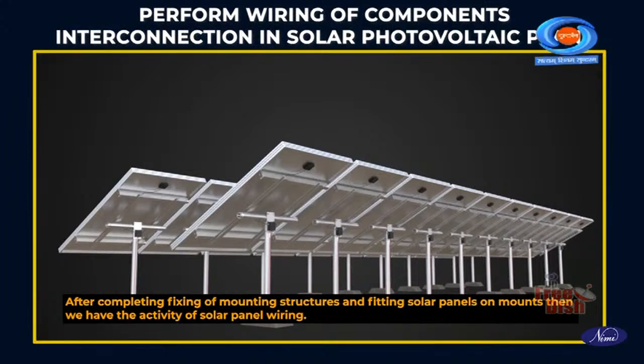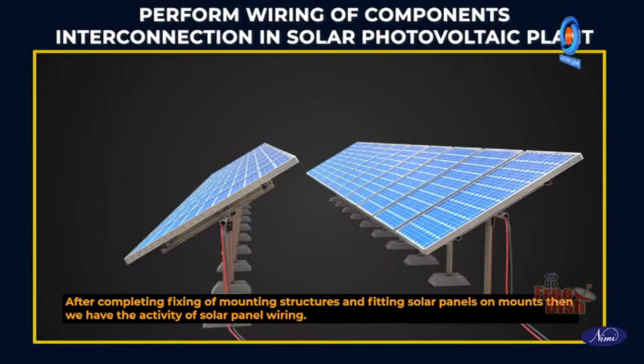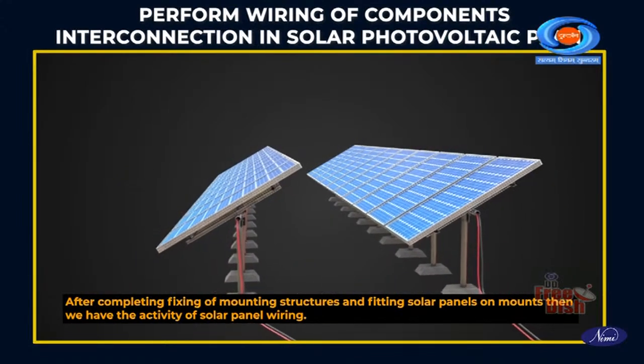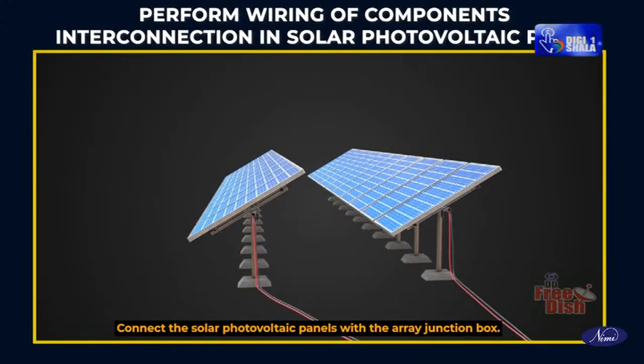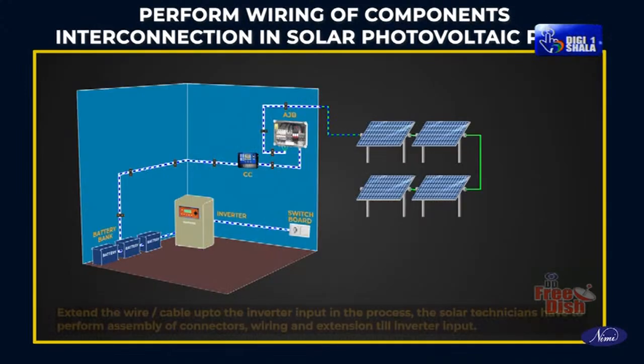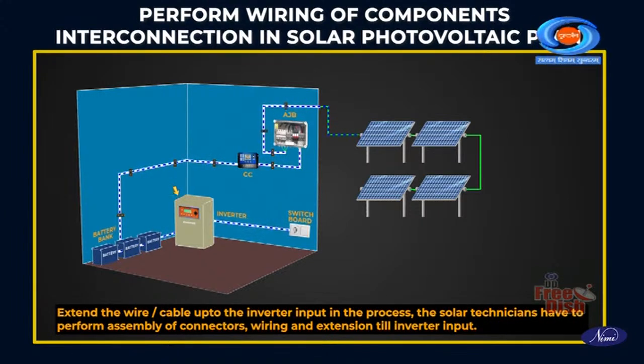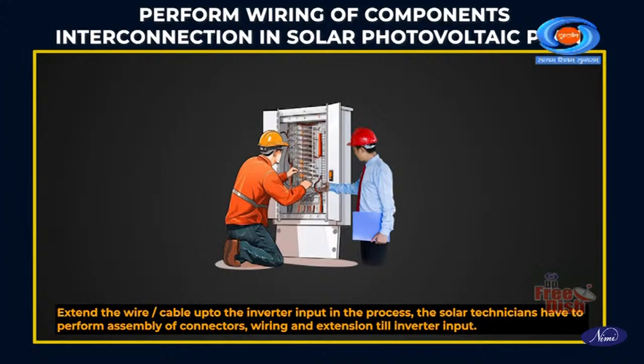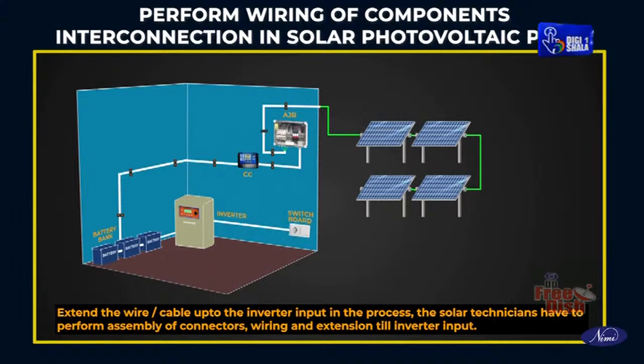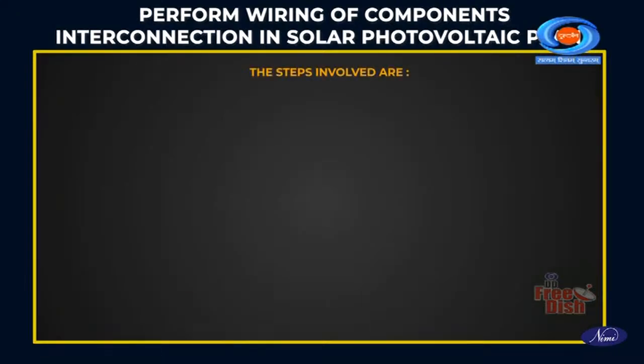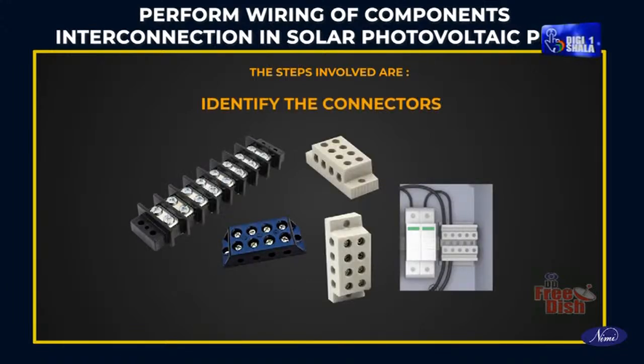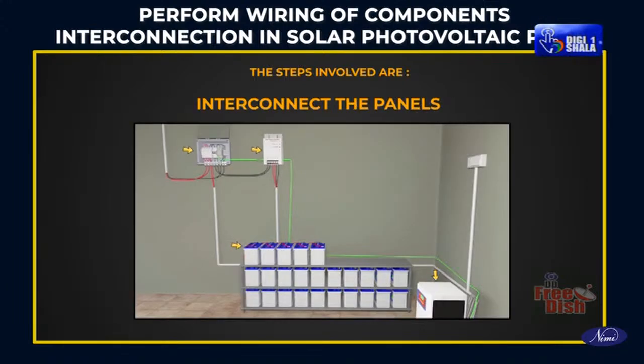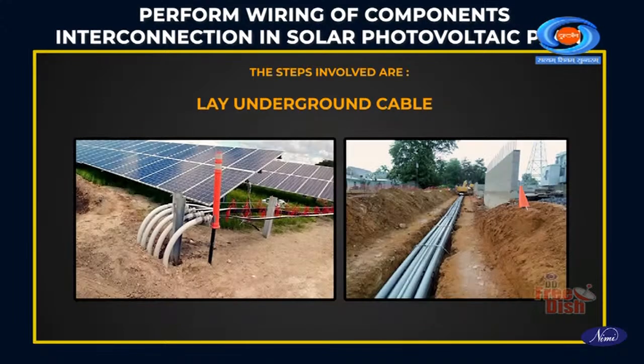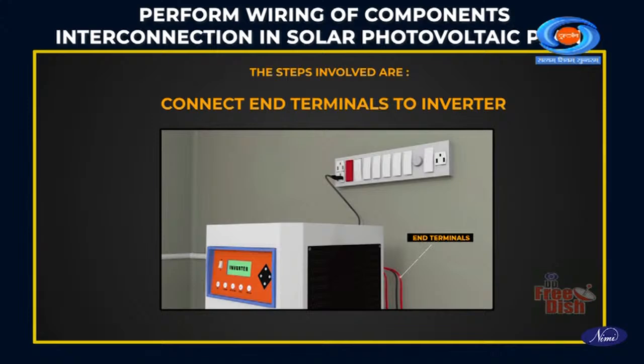After completing fixing of mounting structures and fitting solar panels on mounts, we have the activity of solar panel wiring. This involves connecting the solar photovoltaic panels with the array junction box. Extend the wire or cable up to the inverter input in the process. The solar technicians have to perform assembly of connectors, wiring and extension till the inverter input. The steps involved are: identify the connectors, crimp the terminals and interconnect the panels, conduit pipe laying, lay underground cable, connect end terminals to the inverter.